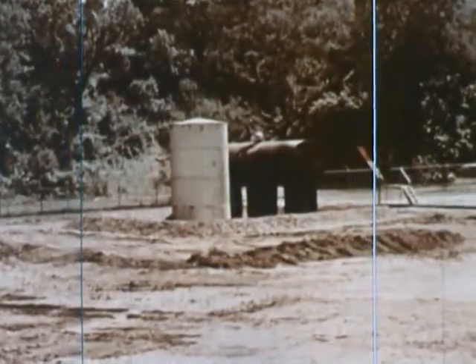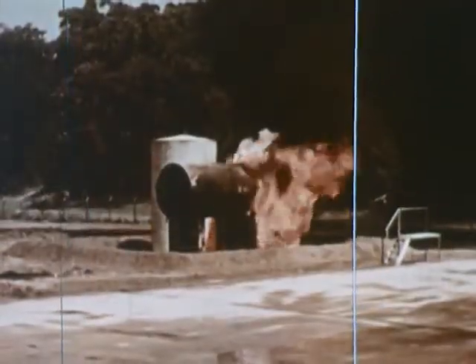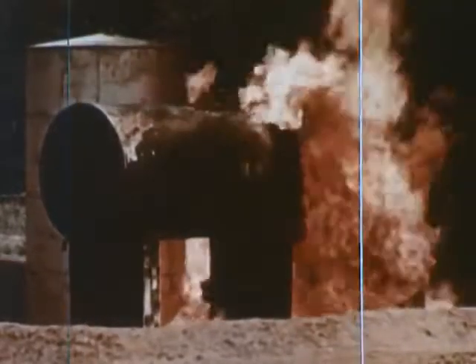In this case, a vertical tank containing 2,000 gallons of gasoline and a horizontal tank still containing 3,000 gallons of gasoline, as in previous fires, are in a common diked area. The horizontal tank has a vent which is adequate for both normal and emergency venting. The vertical tank has a 2-inch vent for normal breathing and a weak seamed roof-to-shell joint for emergency venting. The fire is being fed at a rate of approximately 80 gallons of gasoline a minute.